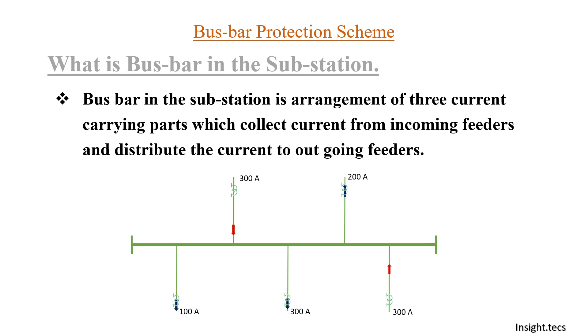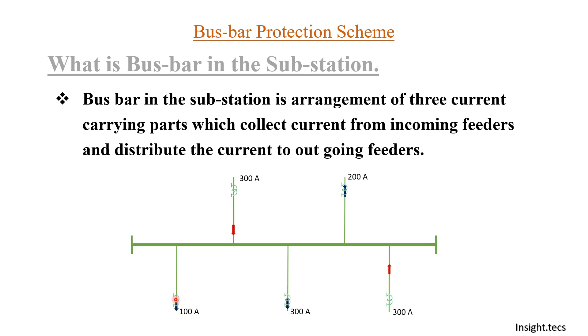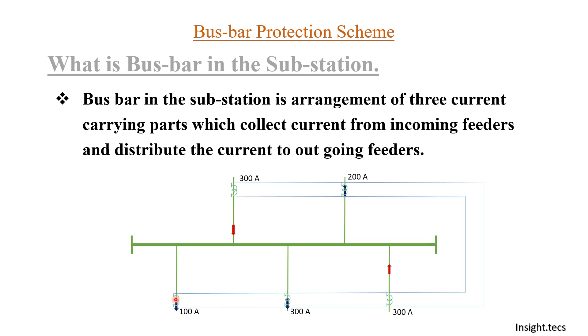Now how does this scheme actually work? We have CTs provided in all the feeders. We connect all the CTs in a particular way and provide one relay. The type of relay and the type of bus bar protection we are discussing here is the bus bar differential scheme. To implement it, we have one differential relay, and we connect all the CT feeders in parallel with the differential relay provided in between them.